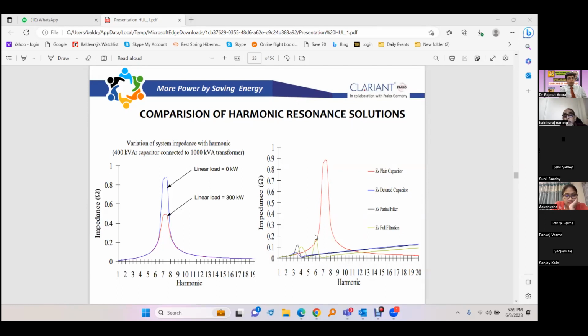This is a curve where we have only capacitor, plain capacitors. There is no reactor used. So there is a curve between impedance and the harmonic frequencies. If we draw, the system impedance will increase, attain a maximum value, and then start coming down. The point where the value is maximum is the point of resonance. And this point should not be close to any harmonic frequency, because that harmonic will get amplified. So here it is happening close to the 7th frequency. This plain capacitor is causing a resonance at the 7th frequency.